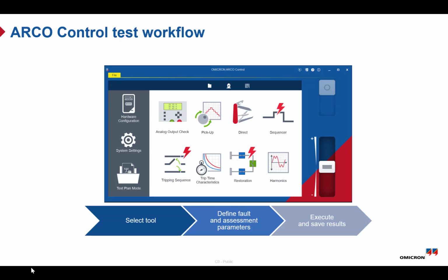Now let us highlight a few key features. The input-output key is used to activate the outputs of the ARCO 400 and apply the test values. You also have a slider control which allows you to adjust values easily without using the keyboard. In the hardware configuration, you define the settings of the controller under test as well as the ARCO 400 configuration. The system setting includes two types of settings. Firstly, application settings, for example, the curve management and the report options. And secondly, general software settings like language and sound. You can also see the test set information, which shows the connected device and the current mode here at the bottom of the screen. There are also helpful shortcuts like access to video tutorials or the last test report, the user manual, and general software information.